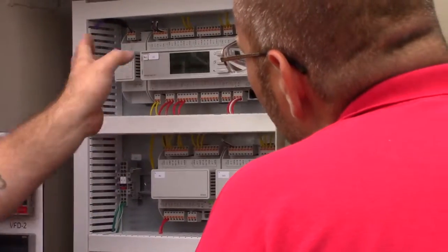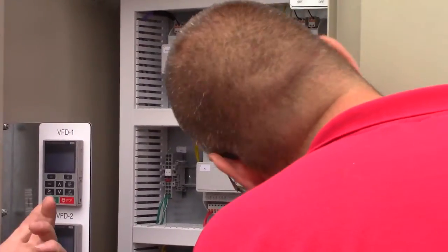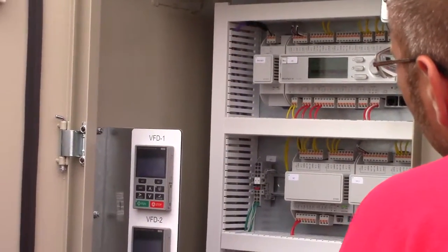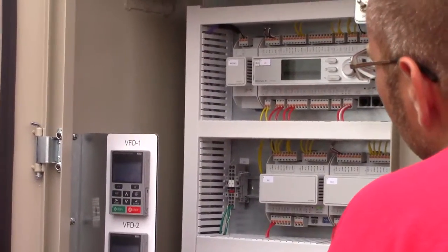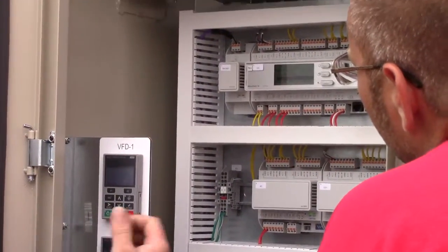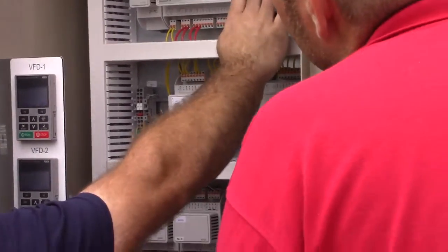Now, depending on how it's set up, I'll take a peek at the setting on this. It could be that it's already set up to be done on the BACnet, which it looks like it is. With that being said, if you adjust this set point and the BACnet's writing to it, that set point's not gonna do anything unless you take the control away from the BACnet. So keep that in mind, that set point in this application right now is not gonna help you any. But there's a lot of good data points just in some of those menus.